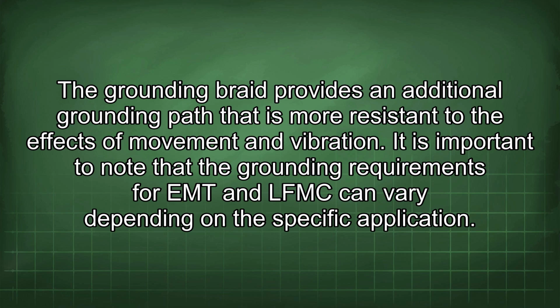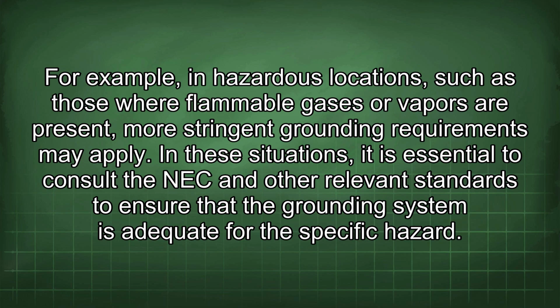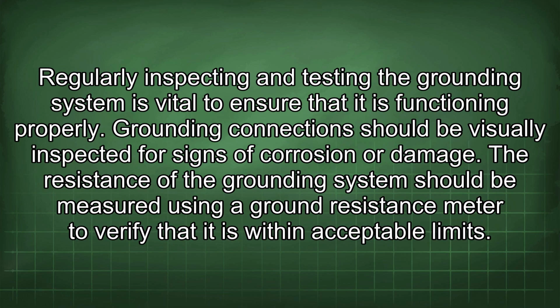It is important to note that the grounding requirements for EMT and LFMC can vary depending on the specific application. For example, in hazardous locations such as those where flammable gases or vapors are present, more stringent grounding requirements may apply. In these situations, it is essential to consult the NEC and other relevant standards to ensure that the grounding system is adequate for the specific hazard. Regularly inspecting and testing the grounding system is vital to ensure that it is functioning properly.